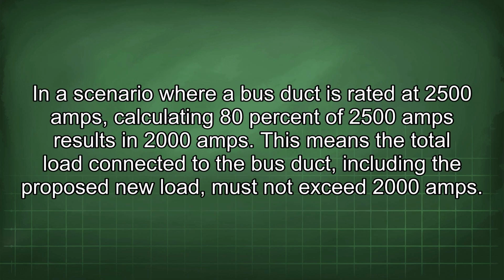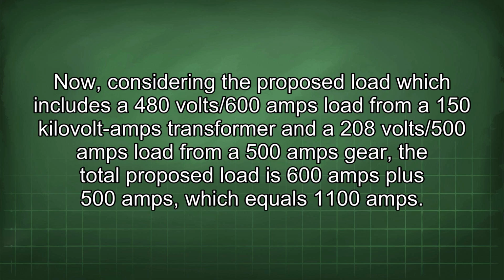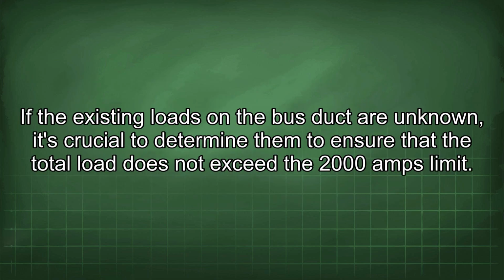In a scenario where a bus duct is rated at 2500 amps, calculating 80% of 2500 amps results in 2000 amps. This means the total load connected to the bus duct, including the proposed new load, must not exceed 2000 amps. Now, considering the proposed load, which includes a 480 volt/600 amps load from a 150 kVA transformer and a 208 volt/500 amps load from a 500 amps gear, the total proposed load is 600 amps plus 500 amps, which equals 1100 amps. If the existing loads on the bus duct are unknown, it's crucial to determine them to ensure that the total load does not exceed the 2000 amps limit.